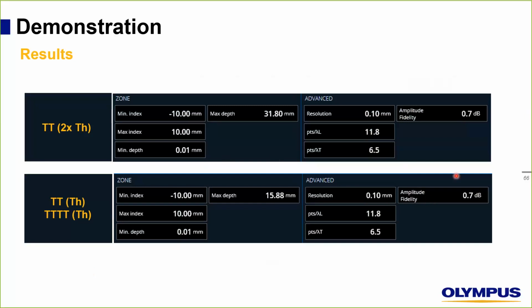compliant? So here we have 0.7 dB when using the TT with doubling the thickness, so it's okay. And this one also, we have 0.7 dB for both groups. So each group has 0.7 dB as amplitude fidelity, same resolution here, nothing changed actually. Even if we are doubling the zone here, actually the only thing that changed is the number of points in the grid. And in the OmniScan X3, this is a really fantastic thing.